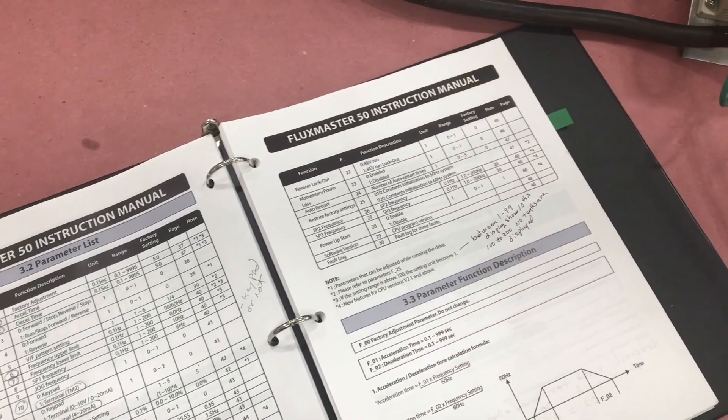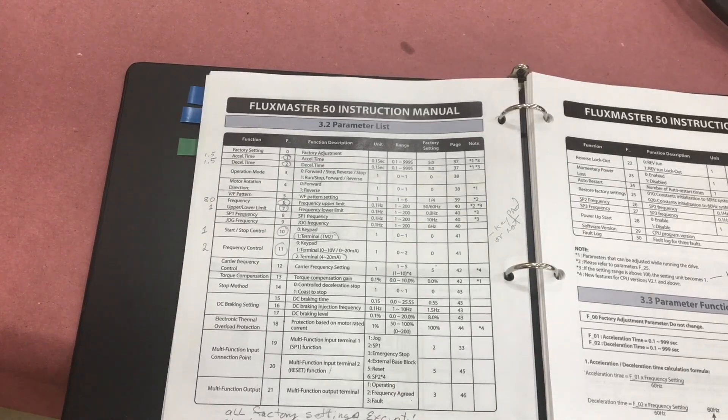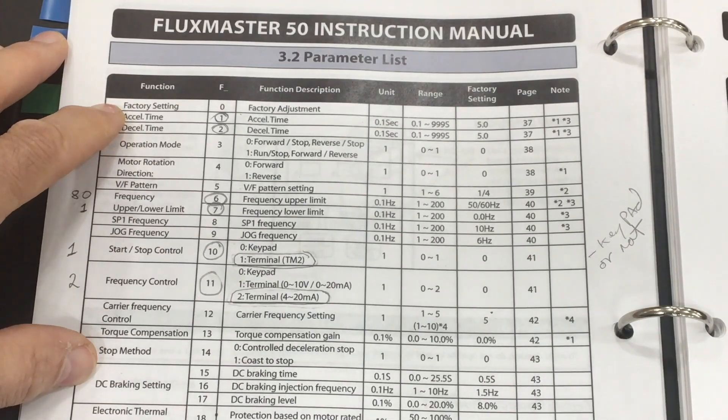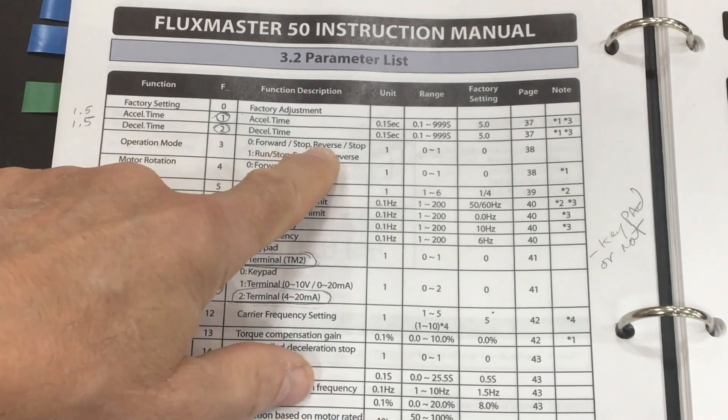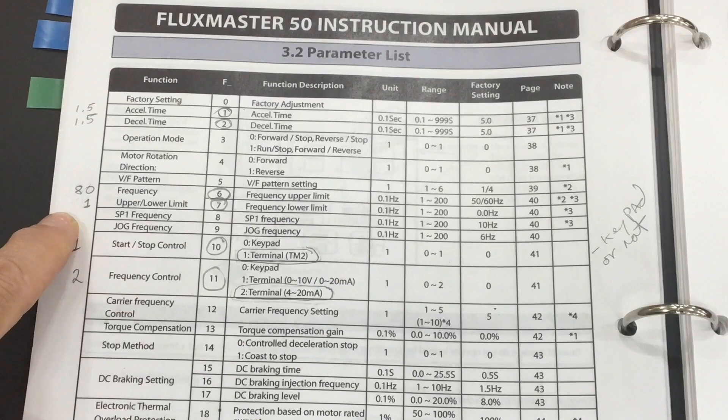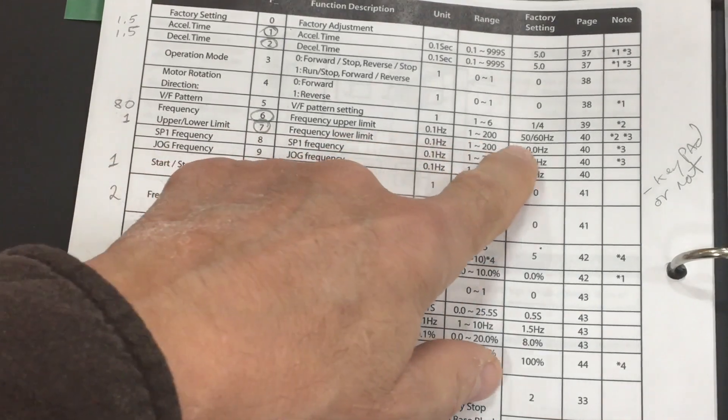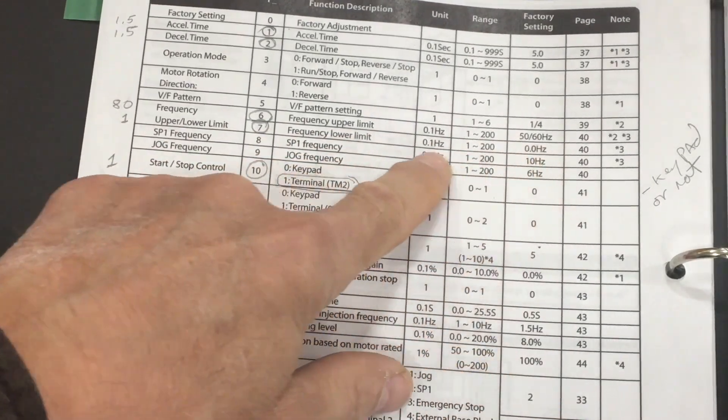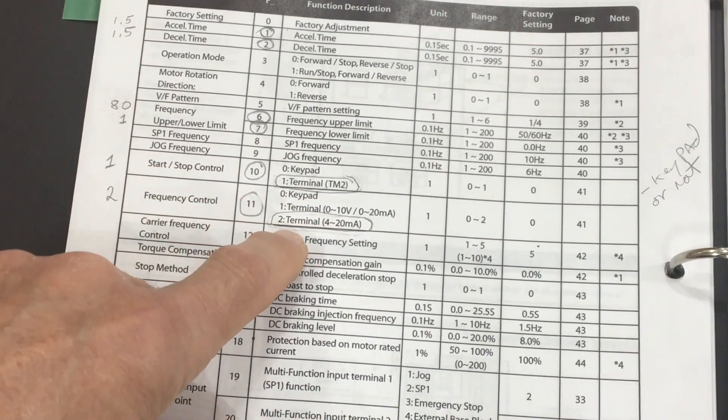This is the manual for the VFD. And there are probably, I don't know, 30 or 35 different settings you could make that are different than the factory settings. And I've changed six. The acceleration time and the deacceleration time is five seconds. Well, we're going to change that to a second and a half. The minimum frequency and the maximum frequency, I'm going to change those to 80 and one. And then finally, I don't want to be running the keypad all the time. So we're going to change that from the keypad to the low voltage terminal instead for controlling the VFD.